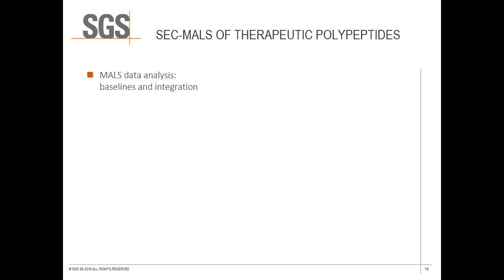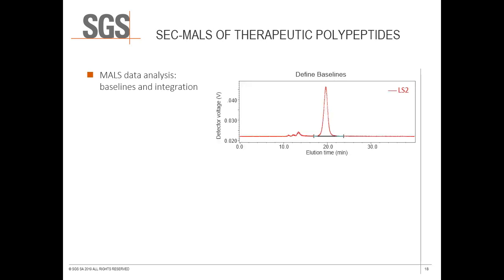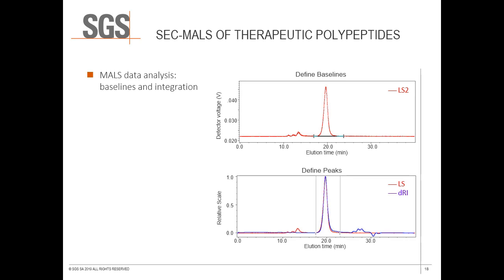With system corrections out of the way, processing of the polypeptide is a relatively simple matter of setting appropriate baselines and integration limits. The uniform peak shape with relatively little tailing seen here is indicative of a separation based solely on the size of the injected molecules and that extraneous interactions are not having a significant effect. The peak is well separated from any interference. The integration limits here are set to include the range in which there is adequate peak area from both detectors to calculate molar mass results.